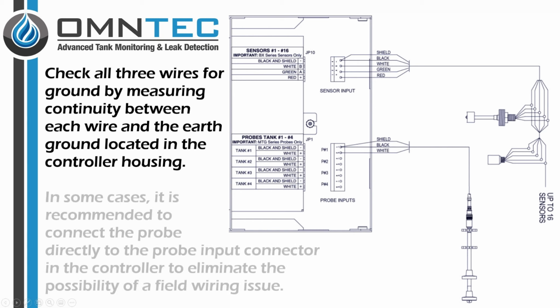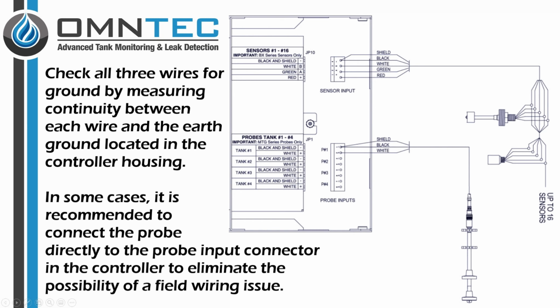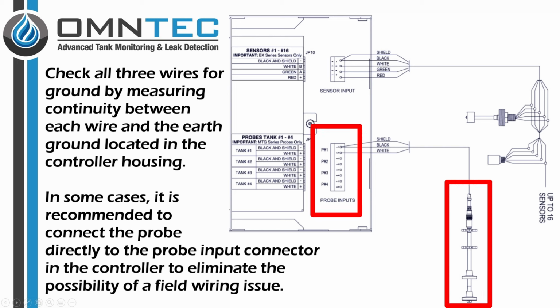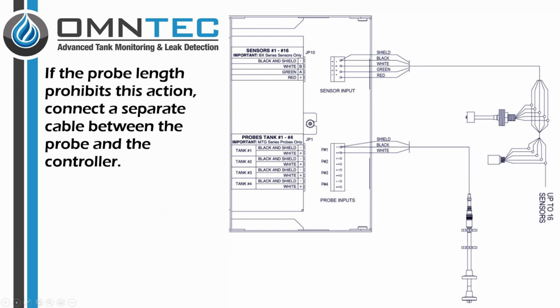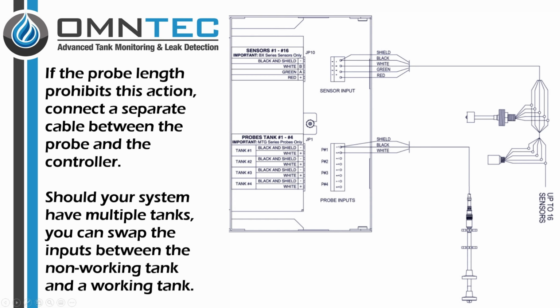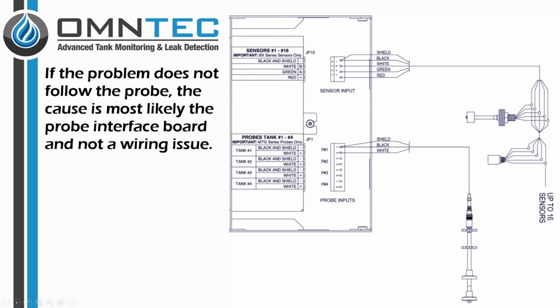In some cases, it is recommended to connect the probe directly to the probe input connector in the controller to eliminate the possibility of a field wiring issue. If the probe length prohibits this action, connect a separate cable between the probe and the controller. Should your system have multiple tanks, you can swap the inputs between the non-working tank and a working tank. If the problem does not follow the probe, the cause is most likely the probe interface board and not a wiring issue.